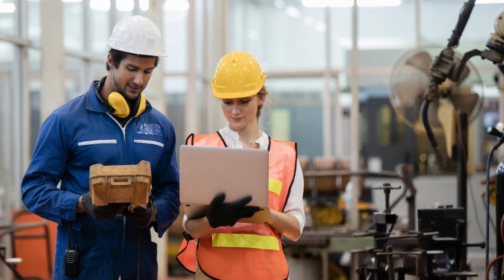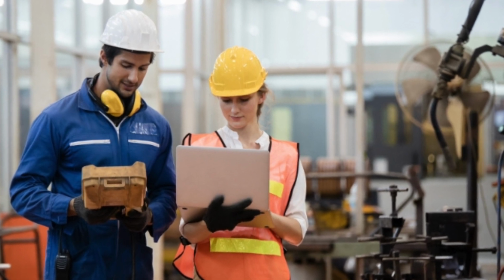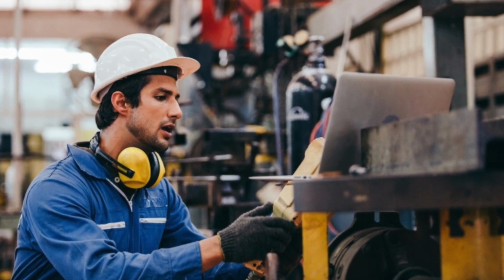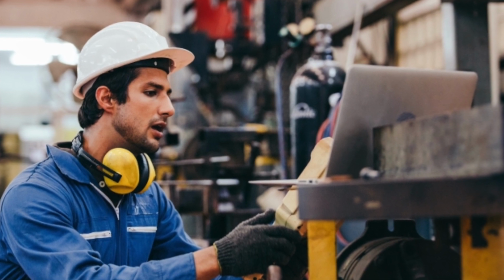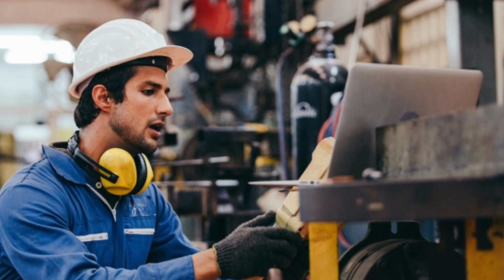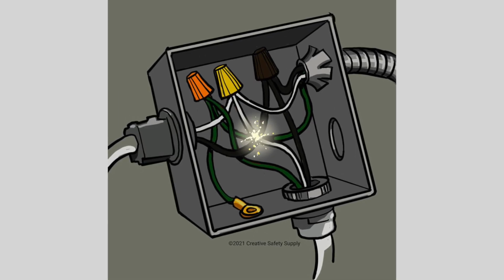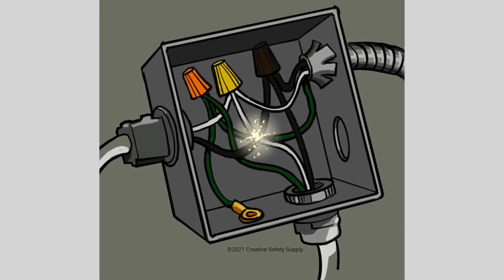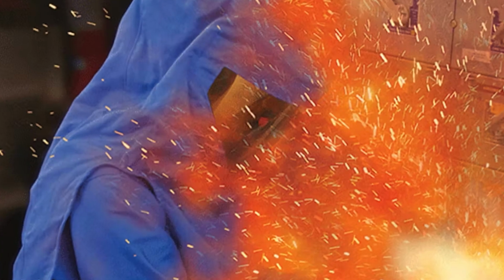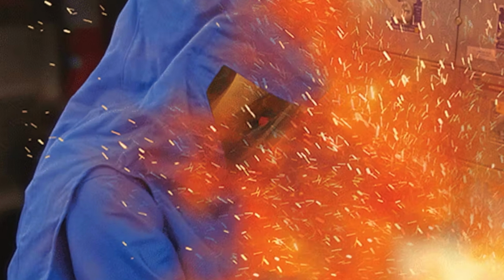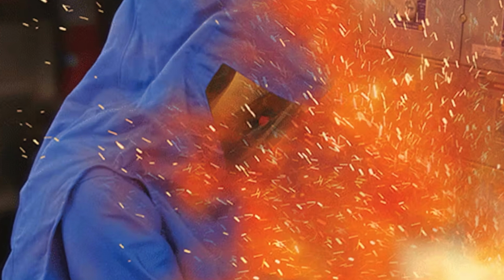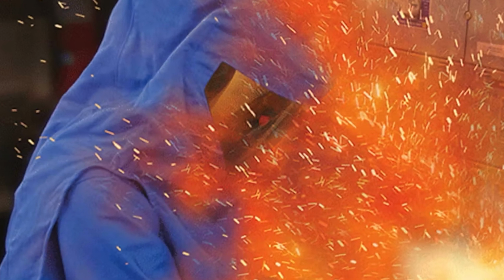If you encounter one of these, while they do not normally occur with 120-volt systems, if you are working with high voltage, you need to be aware of the possibility of an arc flash. Arc flashes occur when a short circuit is created between two points where electricity is being conducted, or between one point of electricity and the ground. Arc flashes can be extremely dangerous. They are essentially explosions and, in addition to the force of the blast itself, produce instant heat and often a shotgun-like spray of molten metal as well.